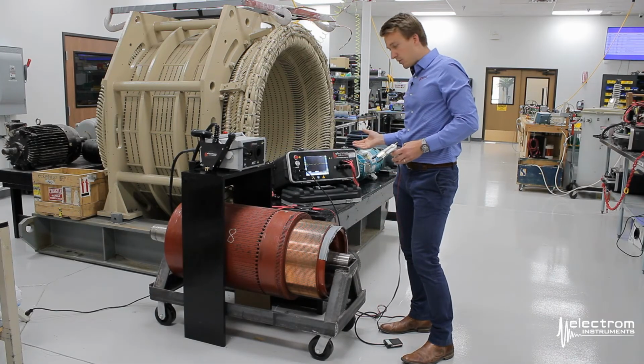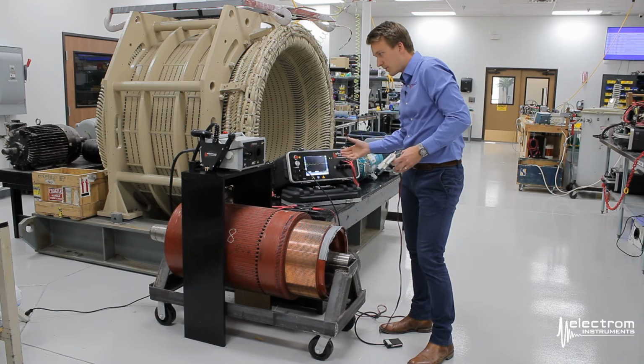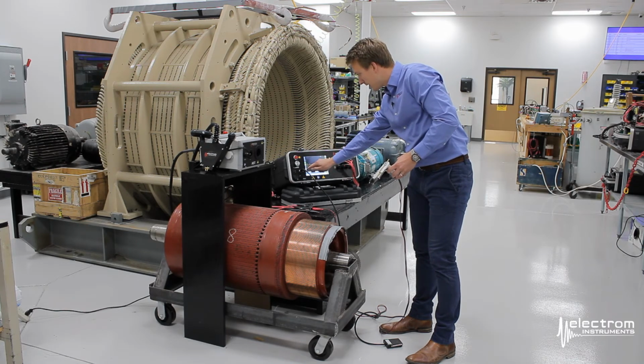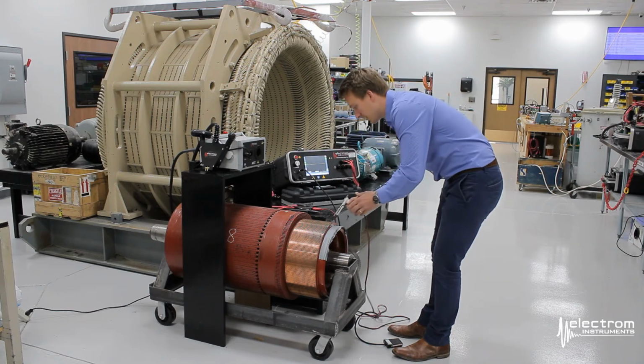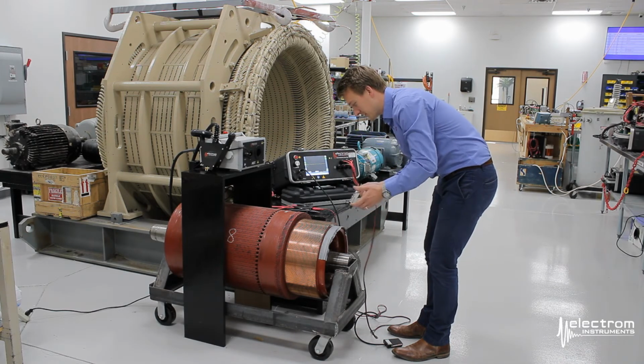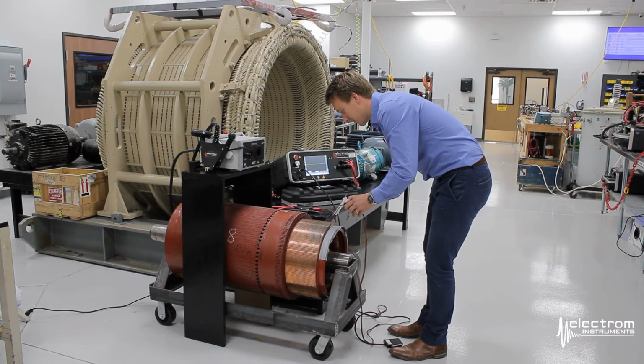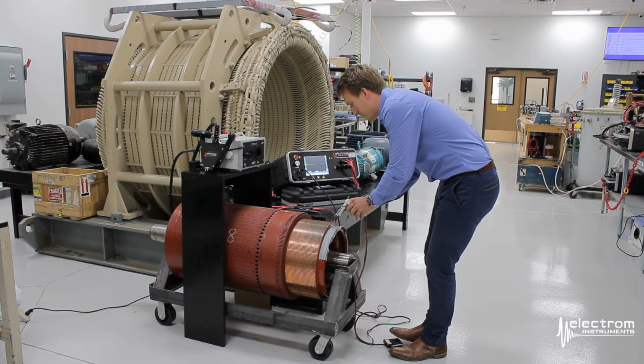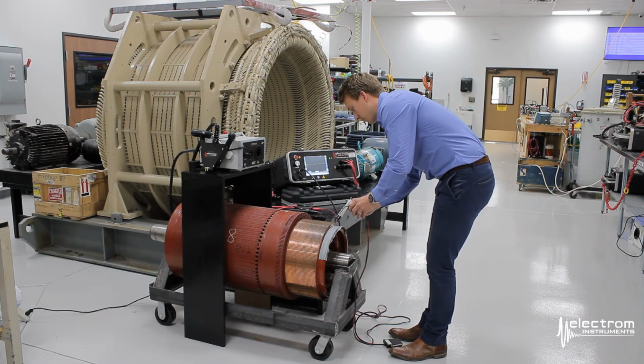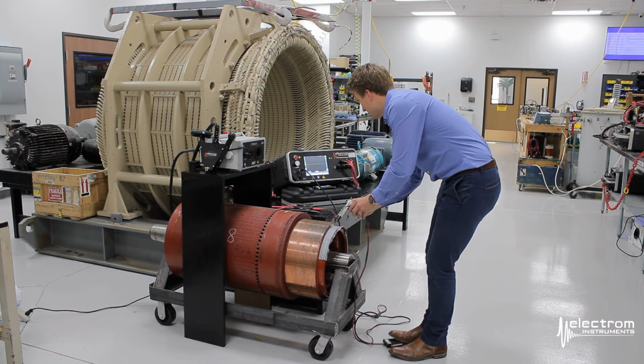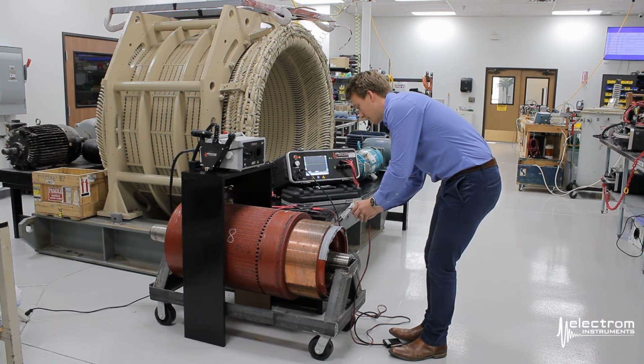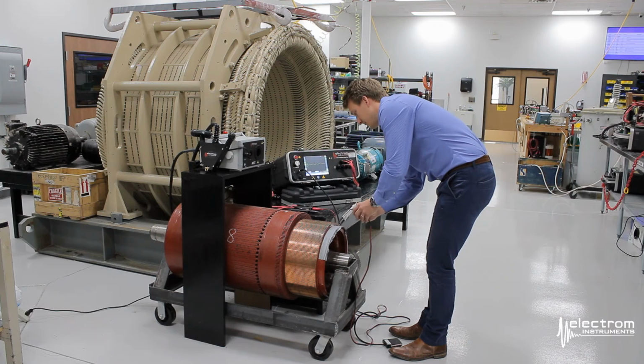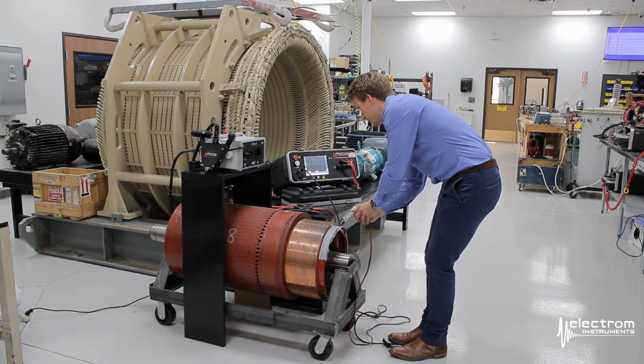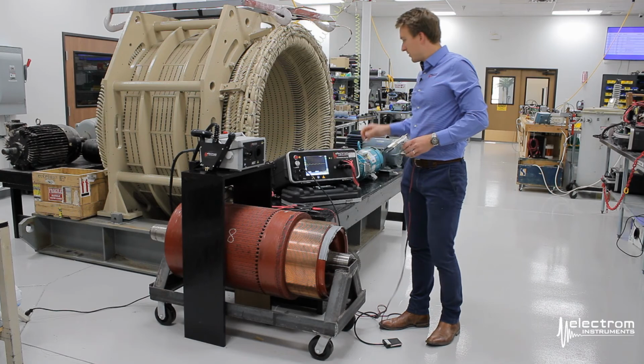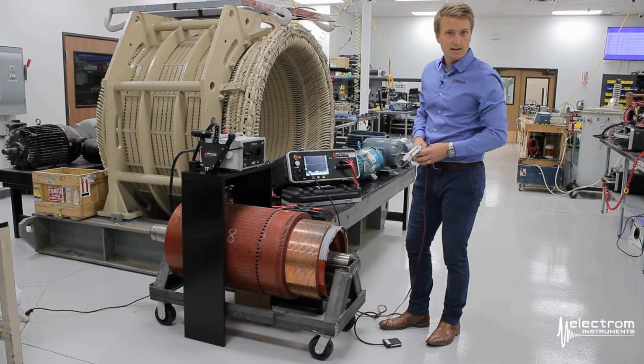If you have the multi-coil feature, then the operation is very similar to what we did with the ABT. You click the next coil button, and I'm going to go back and pretend that we didn't do our additional testing here. So 5 over from our first test, step on the foot pedal, that's coil number 2, then move 5 over again, coil or test number 3, and so on. So having the multi-coil feature is the best way to make sure that you record and represent your test data accurately.